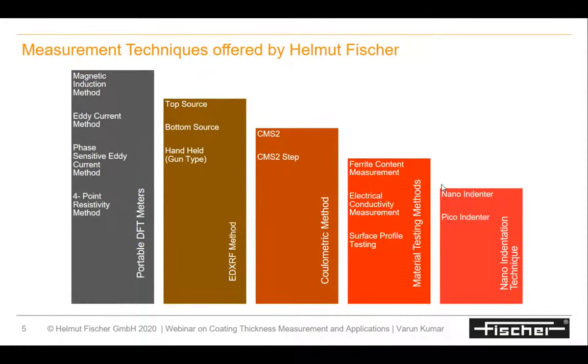When it comes to Fischer, we have five methods of thickness measurement. The first is portable DFT meters — the normal DFT meters used extensively in all industries for paint thickness measurement. There are different principles and we will give a small overview of each. The second is EDXRF, which is for electroplated components — a completely non-destructive test that helps in determining multi-layer plating thickness, material composition analysis, and plating analysis.